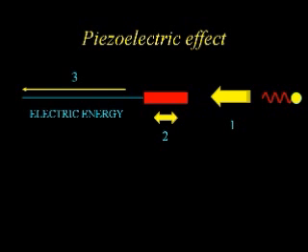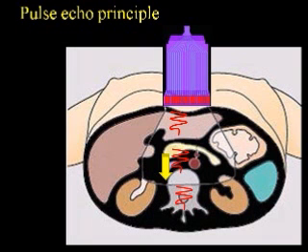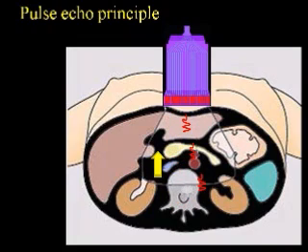This effect is called the piezoelectric effect, and it is the basic principle for producing ultrasound. Now I will explain the pulse echo principle. This is a transducer and this represents a body with internal organs. Once an ultrasound wave is sent out, reflectors which are near to us reflect the ultrasound early, and reflectors which are far away reflect the ultrasound beam at a slightly later time. By timing these returning ultrasound waves, the machine knows from which area or distance a particular signal is coming.